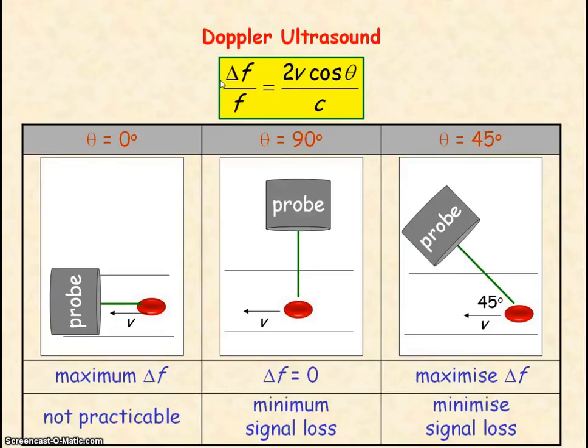For small angles of theta, you will have a large Doppler shift, a large change in frequency. However, the ultrasound will have to travel a greater distance inside the body to reach the blood cells in the artery, so there will be greater signal loss, greater attenuation or absorption of the ultrasound inside the body. As a compromise, an angle of 45 degrees is used in order to maximize Doppler shift but minimize the signal loss, so maximizing the signal that is received by the probe.